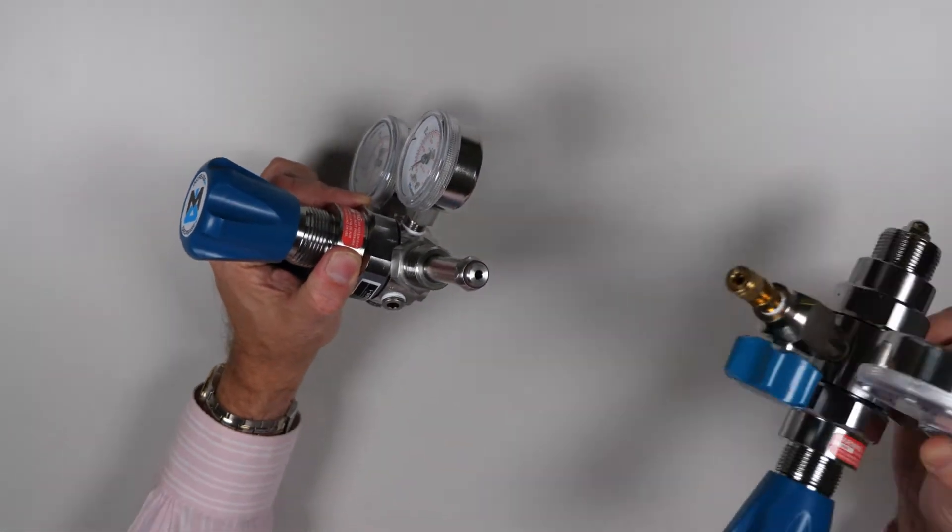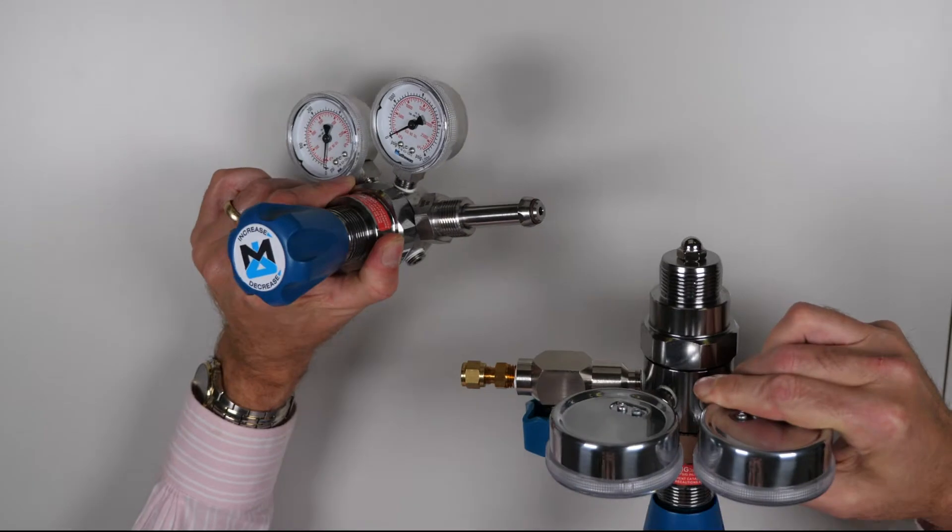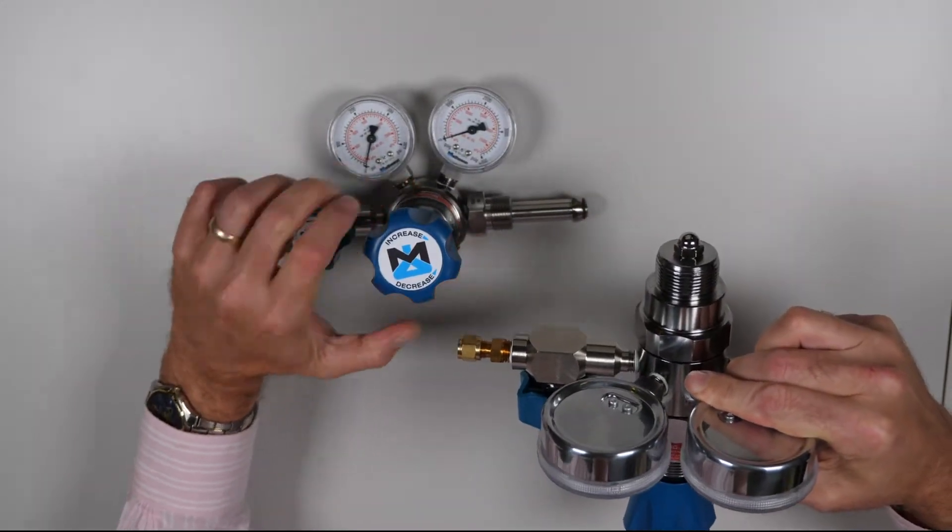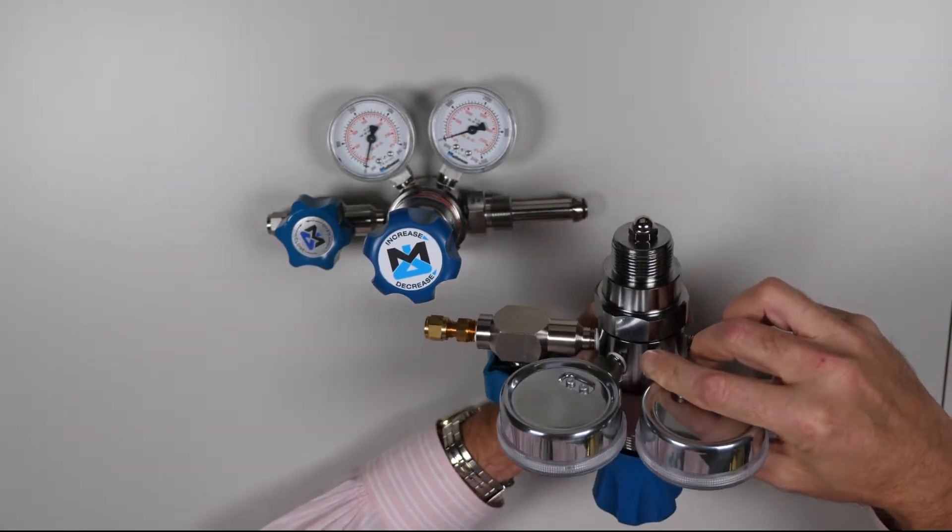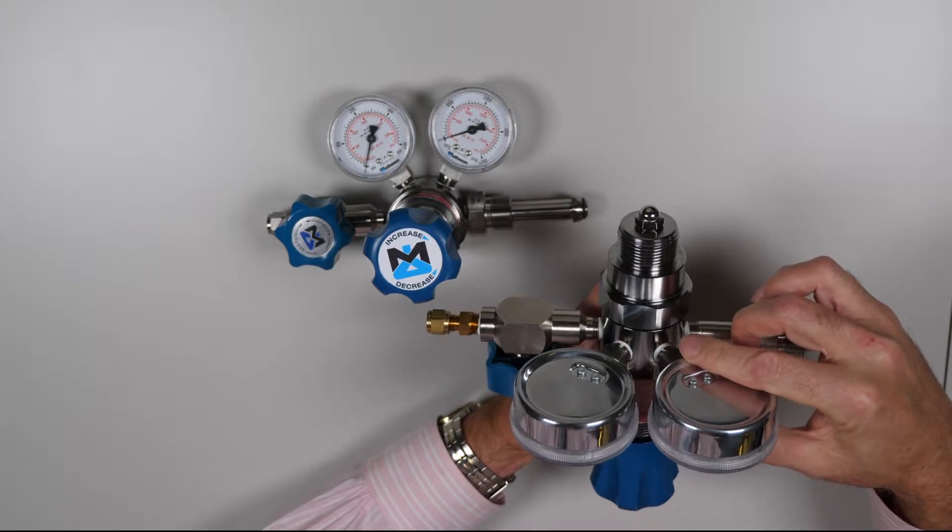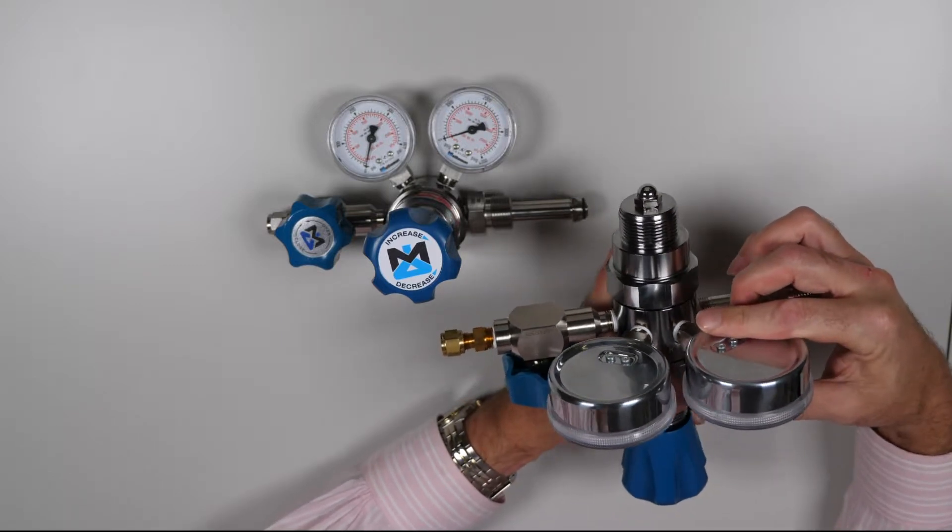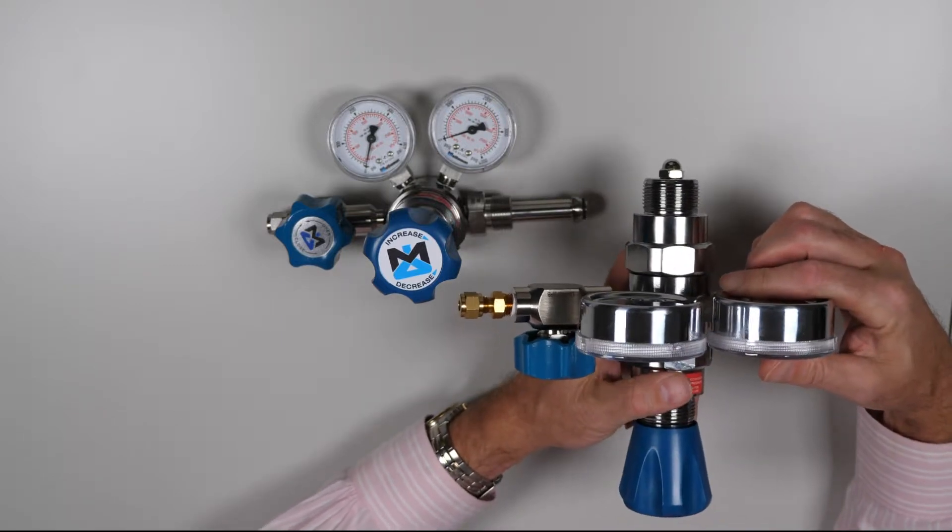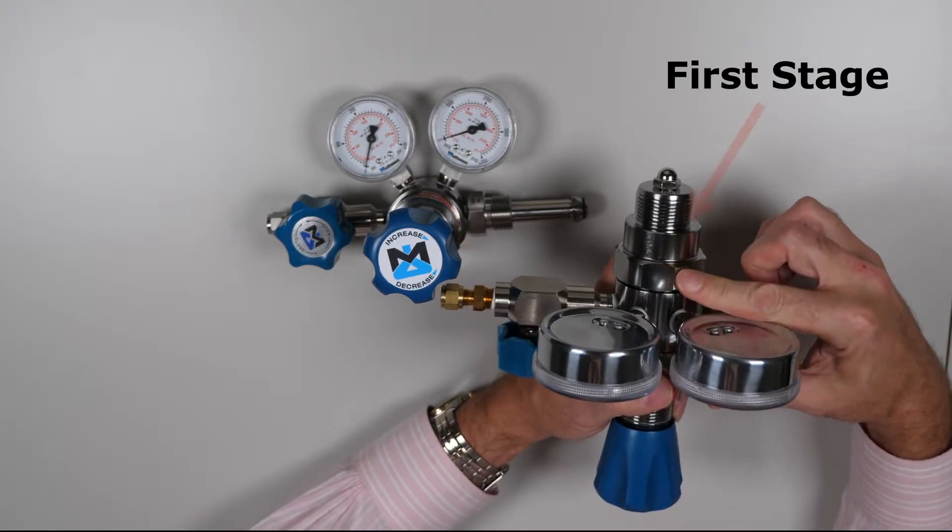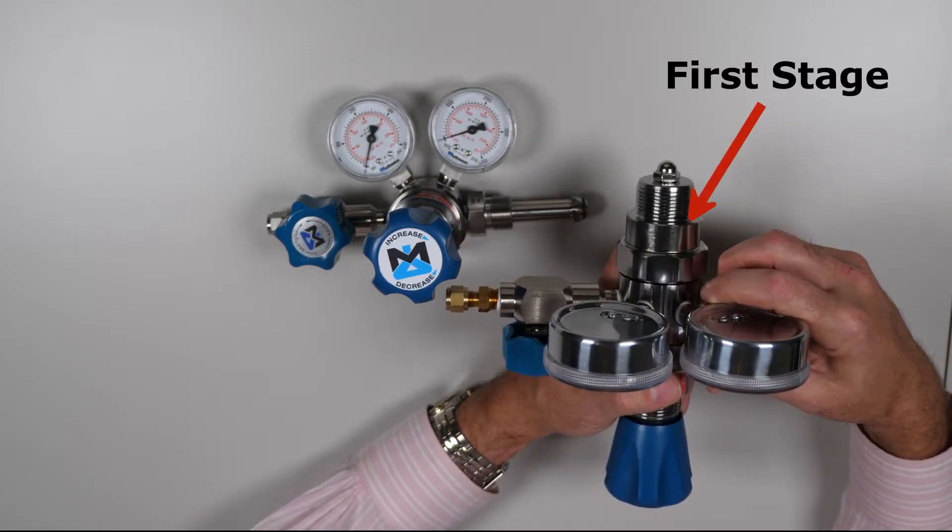This is a single-stage regulator. And this is a dual-stage regulator. Dual-stage regulators are like two regulators in one body and will offer a more stable delivery pressure over the life of a cylinder. The first stage of a dual-stage regulator is set for about 300 psi.